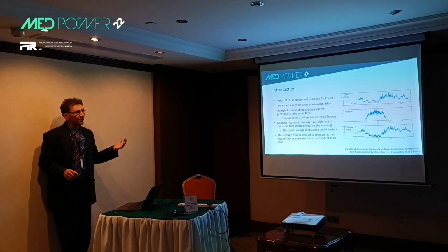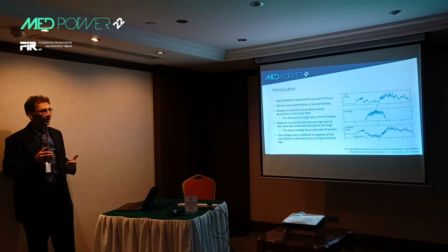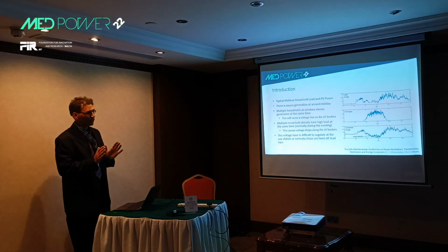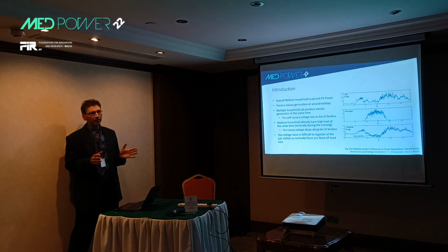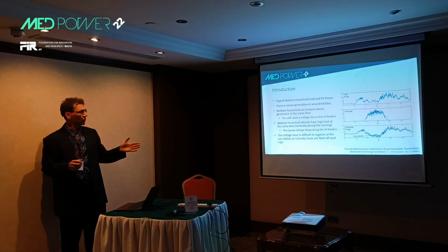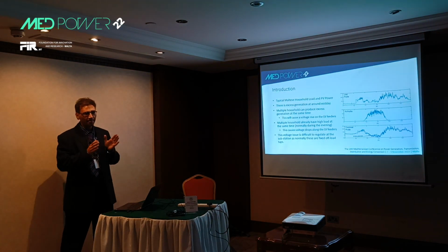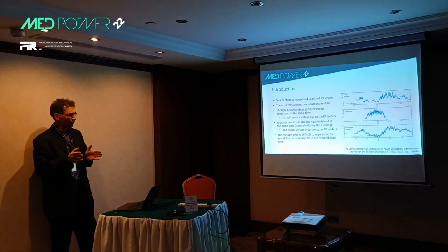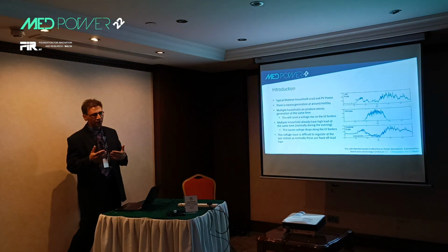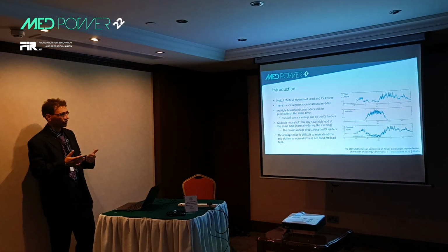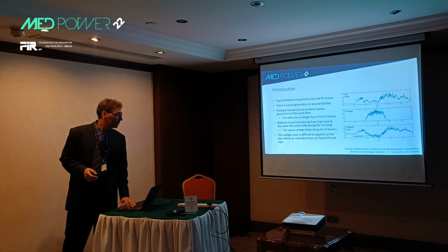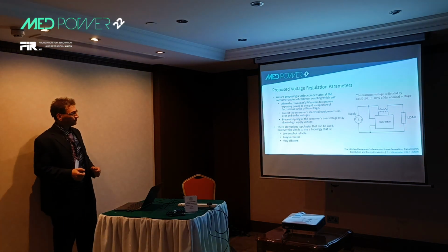So you need something which actively regulates the voltage which the consumer is seeing. Unfortunately, this cannot be done at the substation because most substations have got fixed offload. They can change the tap changers, but this has to be offload. So obviously, it's not something which can be done in real time.